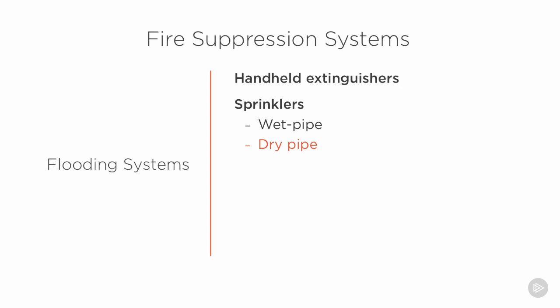We also have dry pipe systems where the actual sprinkler system is just filled with compressed air. And the idea behind that is that the water is held back at a certain riser point and is not released until a fire alarm signal is received. And the advantage of that is that you don't have water in the pipes to freeze, and damage to a sprinkler head would not flood that area, for example. So between wet pipe and dry pipe, there are obviously differences in cost.